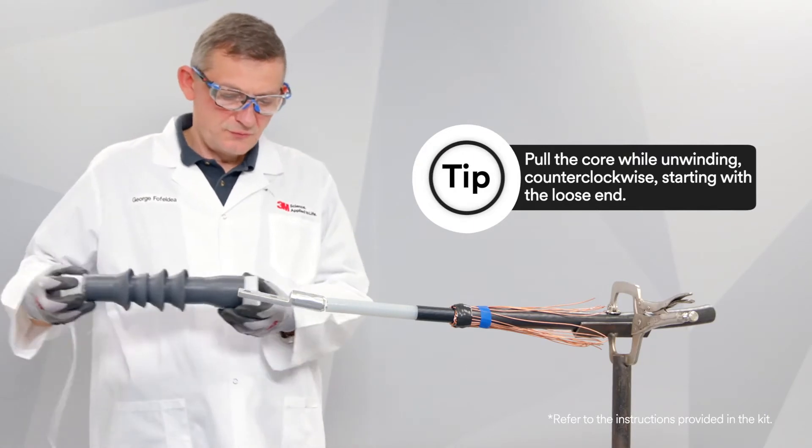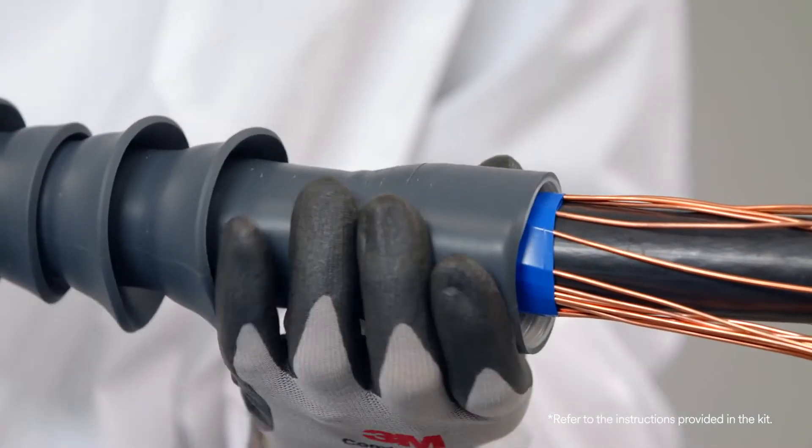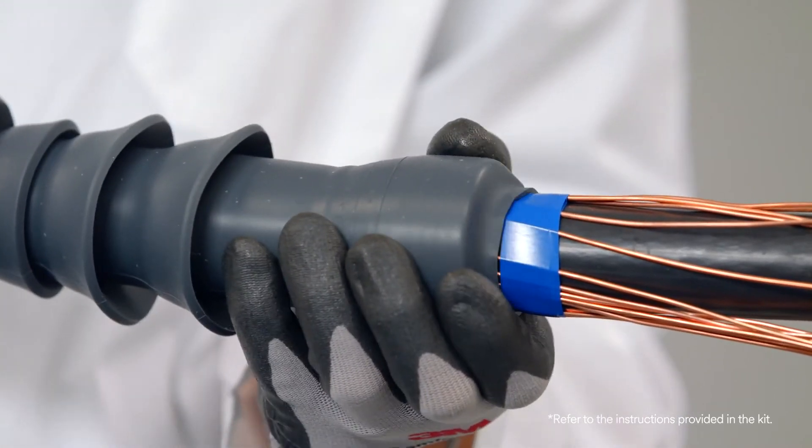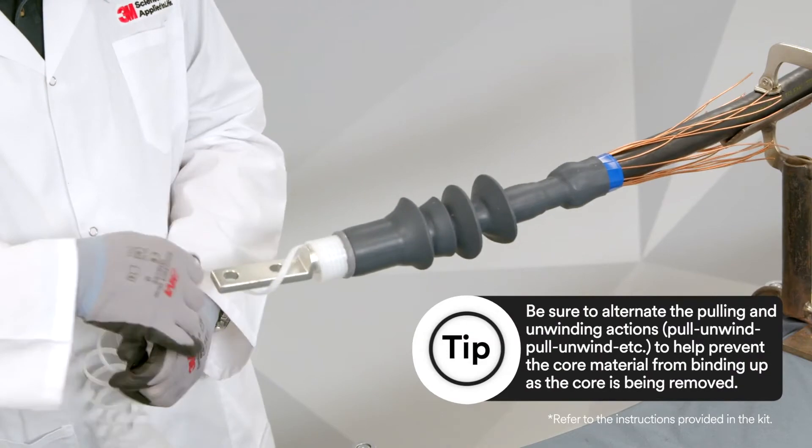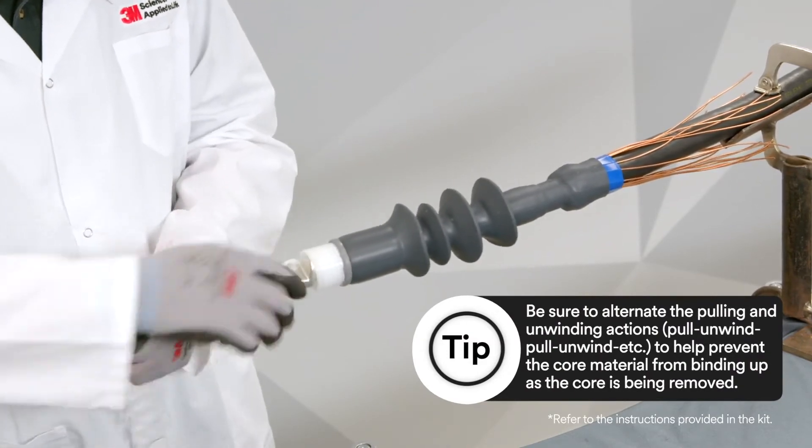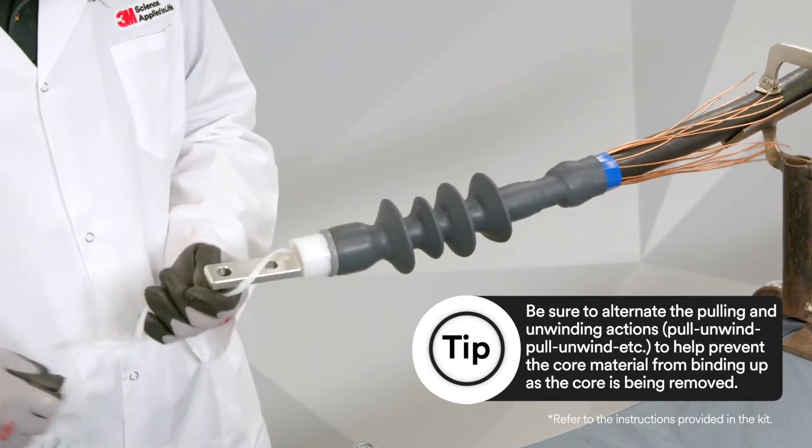Then slide the termination body onto the cable so it aligns to the edge of the marker tape and remove the core. Make sure the termination body, not the core, is right at the edge of your marker tape.